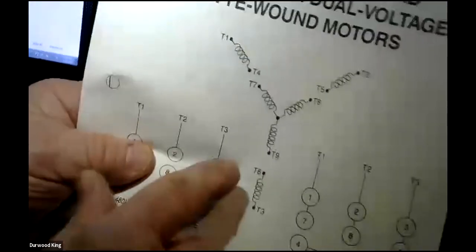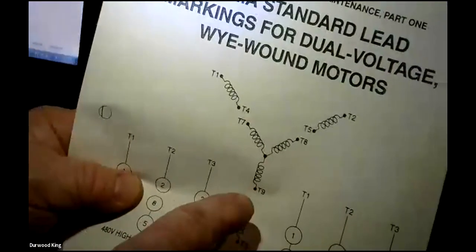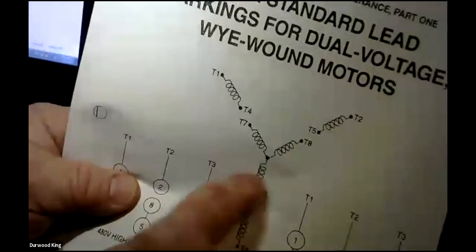I had voltage on all three legs. It wasn't missing voltage going to the motor. All the legs were actually there when I checked them to ground or phase to phase. The motor had the right voltage going to it. But guess what? It was single phasing internally because it had a broken winding on the inside.